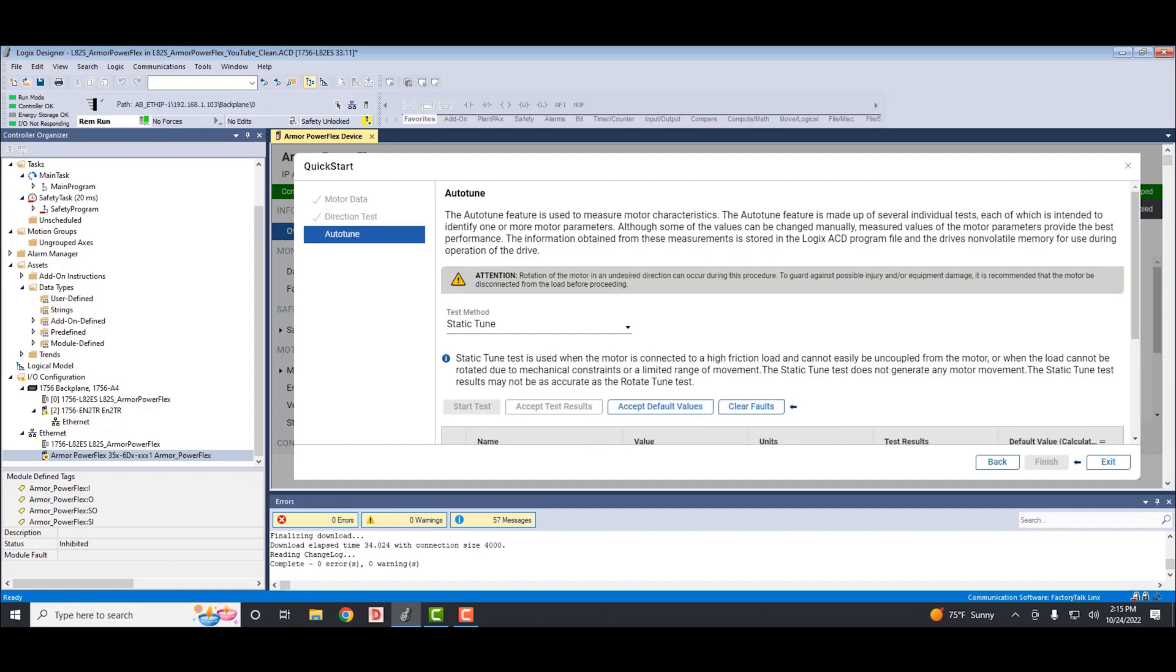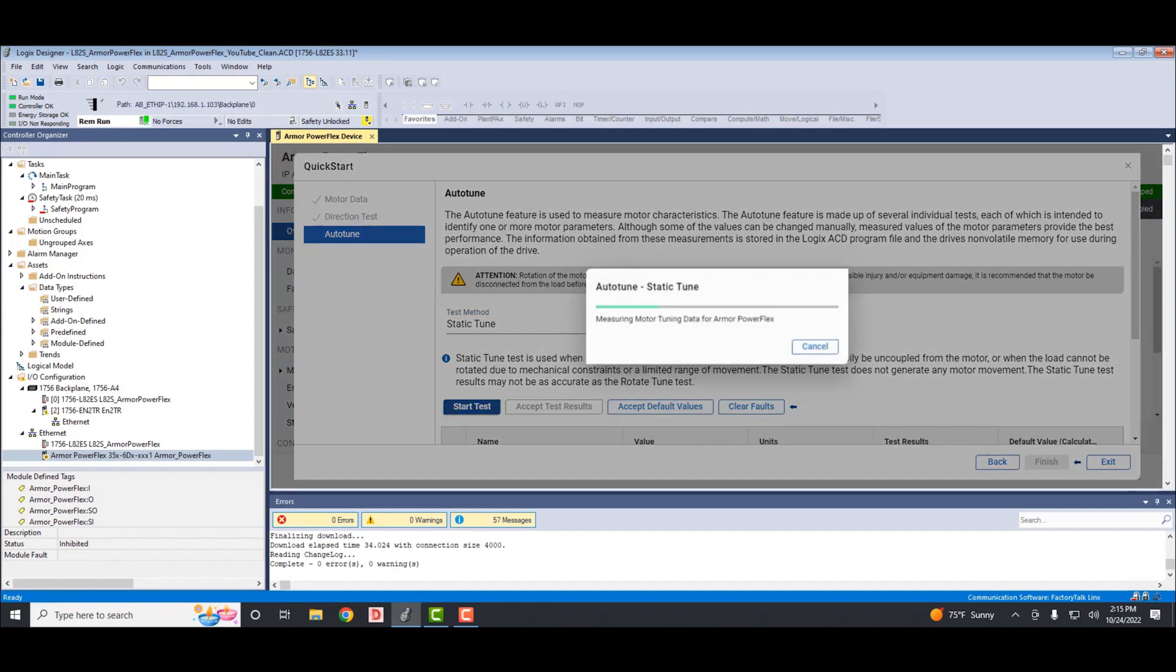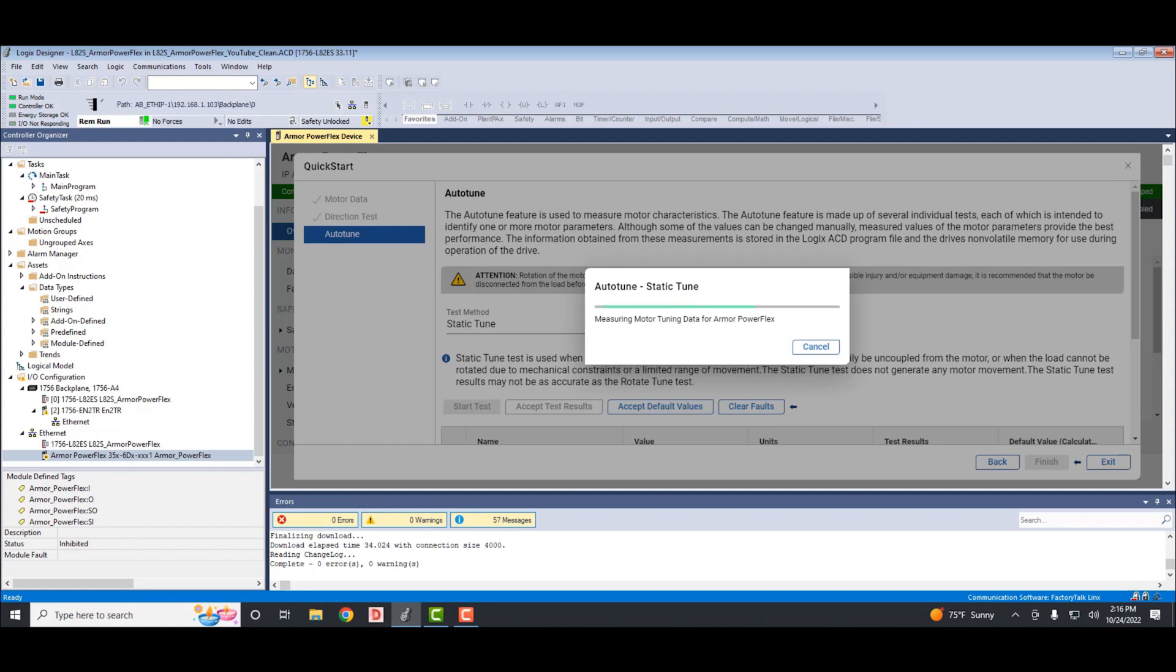This tab allows you to do a tune on the motor. Your two options would be a static tune or rotate tune. With the motor plugged in, I would prefer to do a rotate tune, but I don't have a motor, so I'll select the static tune so we can complete the process. Now keep in mind during this, you can get motor motion, so you might want to be decoupled from any load.